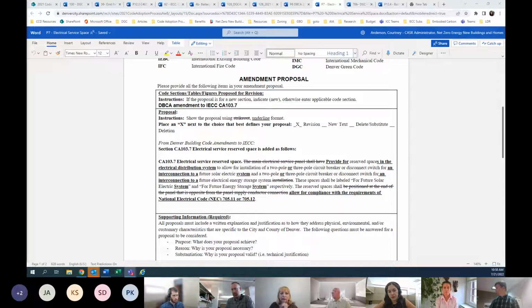I think David has a very valid point on intent, because the way that it was currently written, it is very restrictive. If it follows the NEC language and the language that David has added, it gives them more flexibility on whether interconnections shall be at, instead of just the main electrical service panel, it could be at another panel that may be more convenient for the system. A lot of times they want to connect on the supply side of the main service breaker or overcurrent device, which the way it's written right now would preclude.